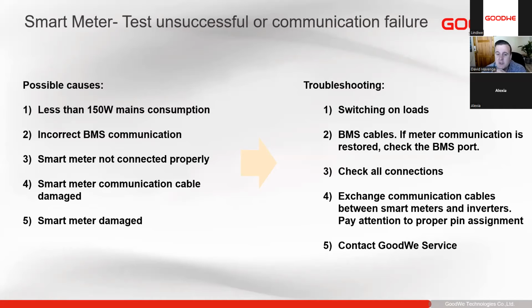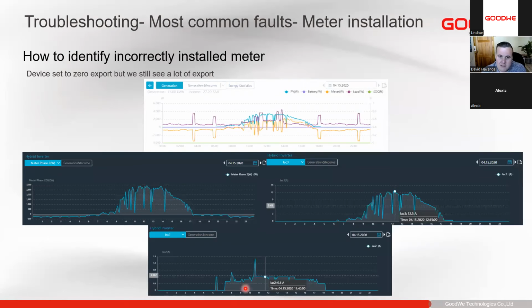If there's a problem with the BMS communication, if the BMS is not connected correctly or there's anything like that, the meter test can fail as well because it tests the BMS communication as well as the meter communication. Sometimes the meter might not be wired up correctly. It would generally say CT connection fault or CT reversed or anything like that. But like I say, you can always double check on SEMS portal as well to see whether everything looks correct. Like I say, the B meter phase 1, phase 2, phase 3. Normally you'll install a little bit before, then you can connect it online to the SEMS portal and then go and view that everything is correct there.